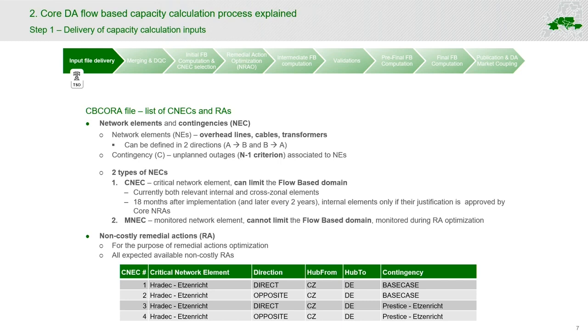The CBCORA file also includes the non-costly remedial actions. These are changes in the grid topology and/or phase-shifting transformer adjustments. They are provided in the CBCORA file and are used later on during the process of optimization of non-costly remedial actions. TSOs have to provide all expected available non-costly remedial actions to the process.